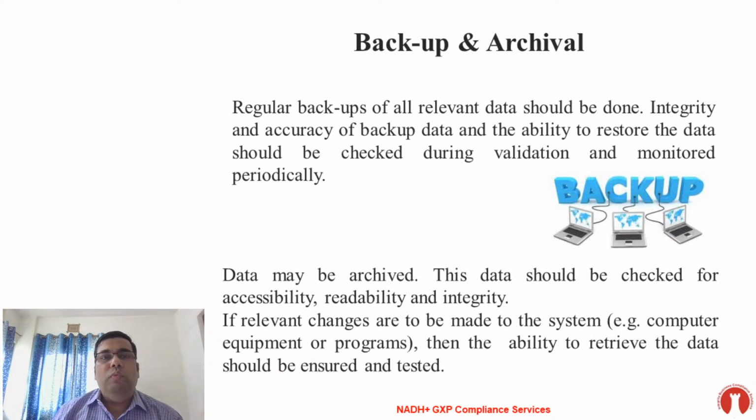Okay, so the point is whether the data is really getting archived on the server or not, and after archival, whether a backup is taken or not, and whether it is retrieved afterwards or not. That is not checked by many companies. They only focus on the software functionality, controls, privileges, and access on the software. This is where many, even the external vendors, are lacking, and most of the site people only go on signing the files. So that is why many companies are getting this observation.